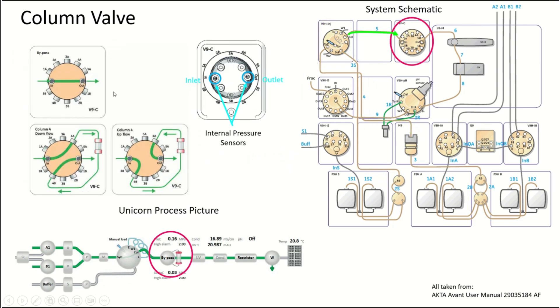Alright, so the column valve has an internal pressure sensor on the inlet and outlet side. This is what gives you your delta column pressure.